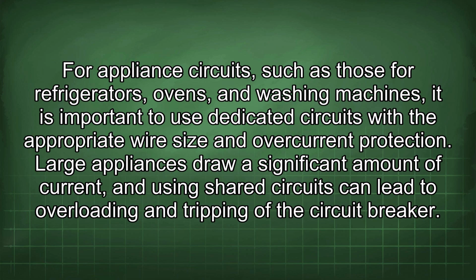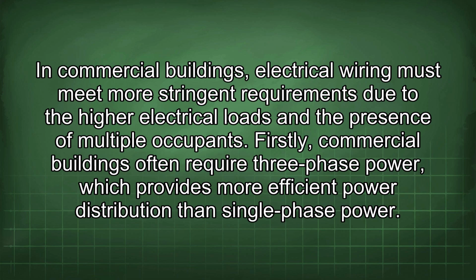For appliance circuits, such as those for refrigerators, ovens, and washing machines, it is important to use dedicated circuits with the appropriate wire size and overcurrent protection. Large appliances draw a significant amount of current, and using shared circuits can lead to overloading and tripping of the circuit breaker.